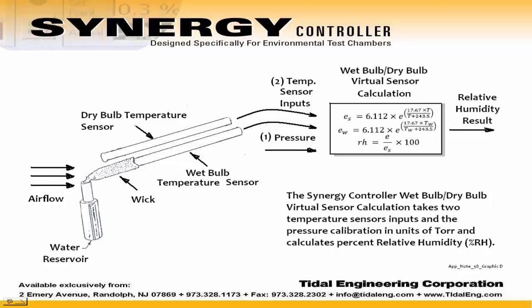To make these measurements, a wet bulb sensor infers the amount of moisture in the air when the evaporation from a moist cloth wick placed over the sensor lowers its temperature reading. When the air surrounding the wet bulb sensor is dry, evaporation of moisture from the wick is faster than when the air is moist. If the air is saturated, no evaporation from the wick occurs and the temperature of the wet bulb sensor is the same as the temperature of the dry bulb sensor.